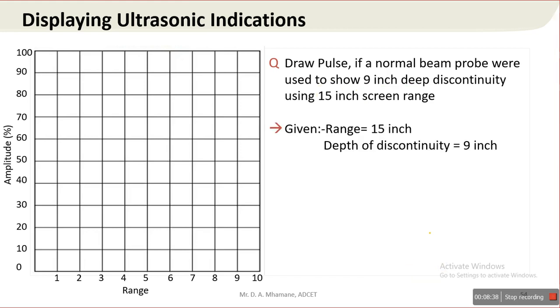So it is given range is equal to 15 inch. Depth of discontinuity is 9 inch. So here, as the screen has 10 divisions on the x-axis, 10 divisions equal 15 inch, because the range is given as 15 inch.